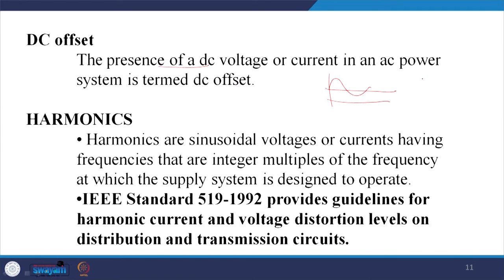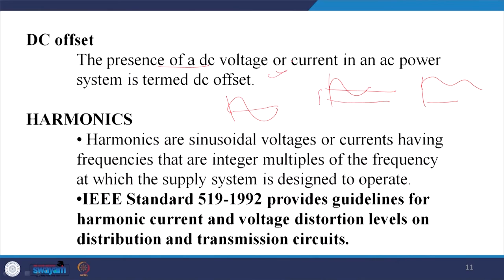DC offset is the presence of a DC voltage or current component in an AC power system. If you feed a DC voltage along with AC, the resultant will carry a DC offset. It also occurs when positive and negative areas of the waveform are mismatched, which happens when triggering pulses are not symmetric. DC offset can generally be eliminated by properly switching thyristor-based devices and keeping the positive and negative areas equal.